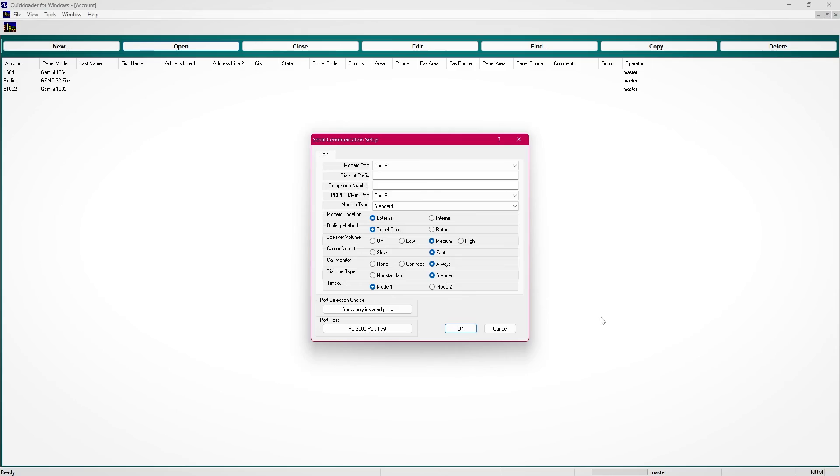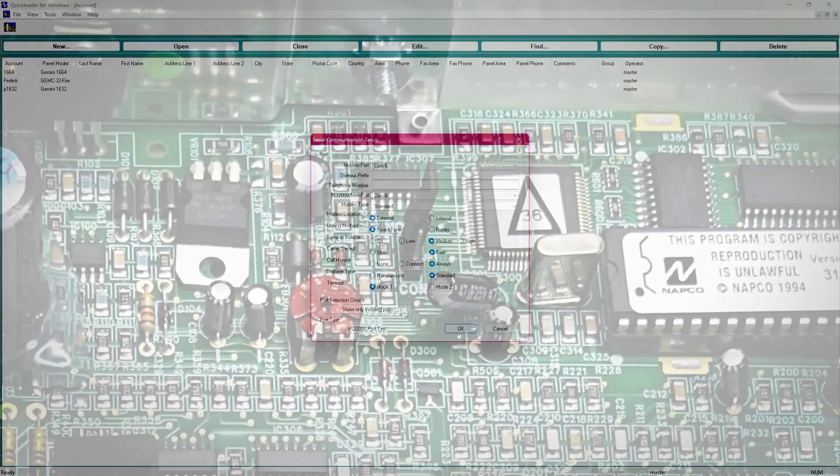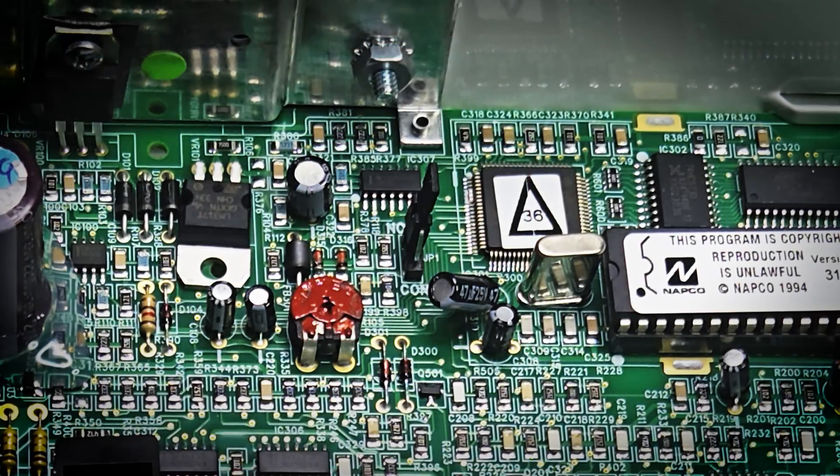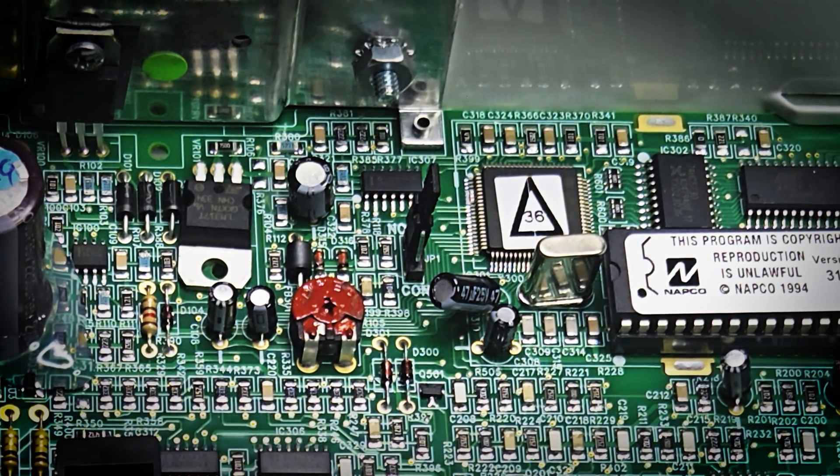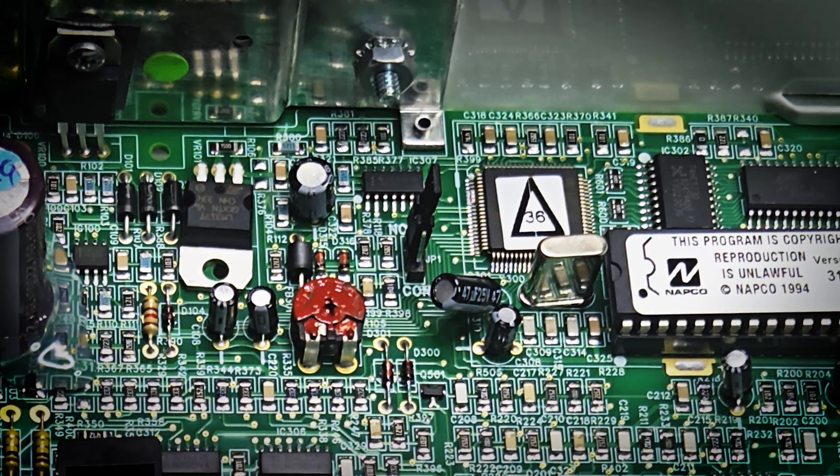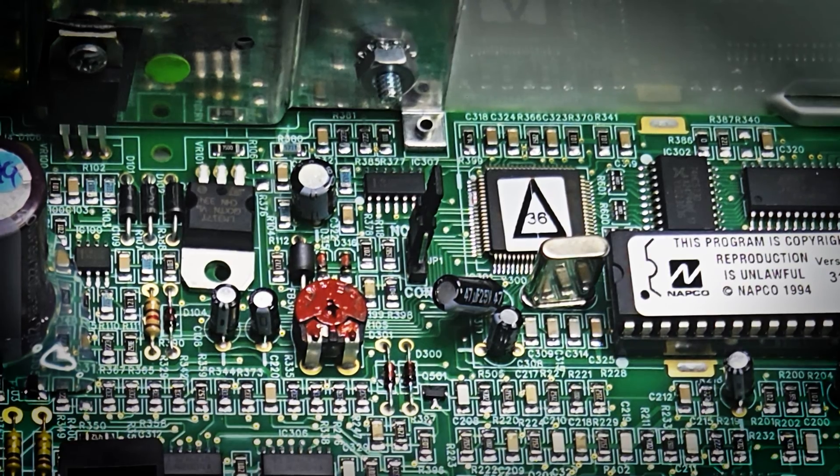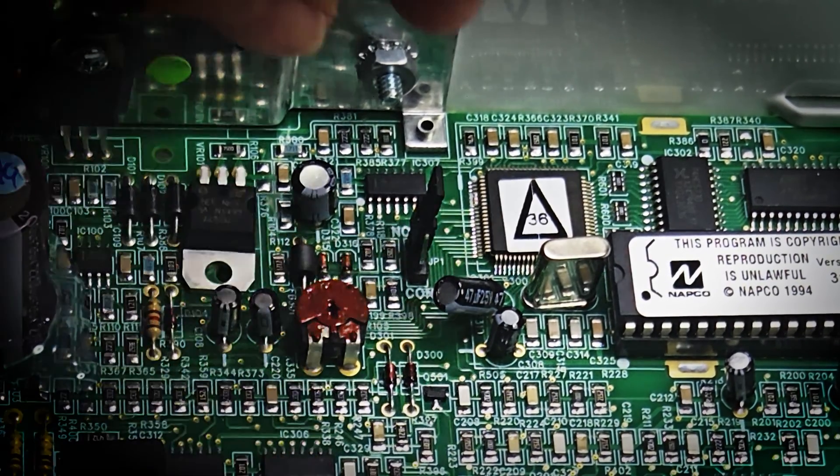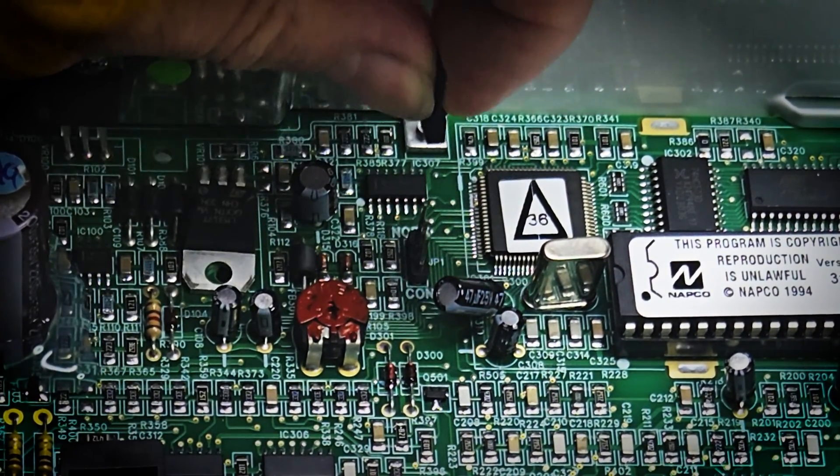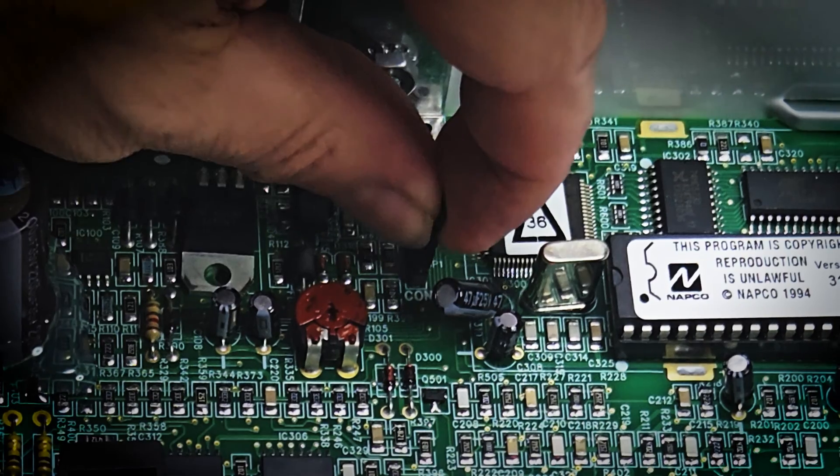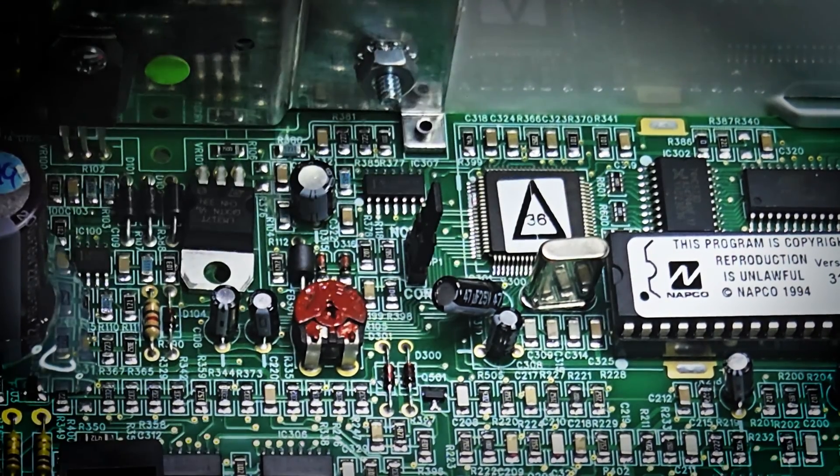Another cause of this timeout is the config jumper on the panel. When attempting to download to your panel, make sure the jumper is set to normal and not config. Remember, normal is in the up position.